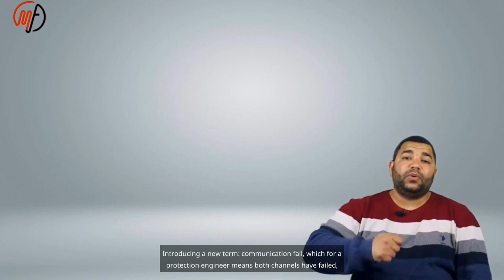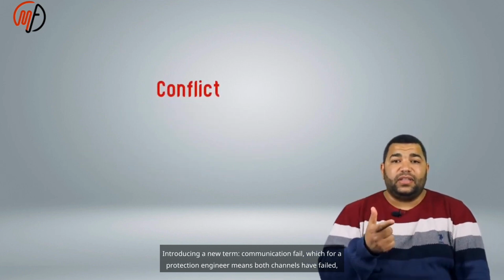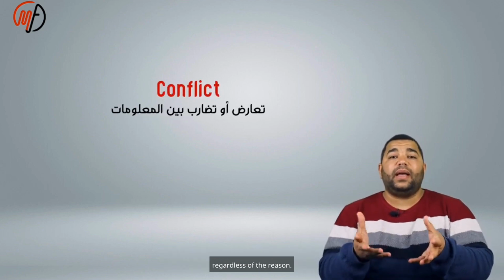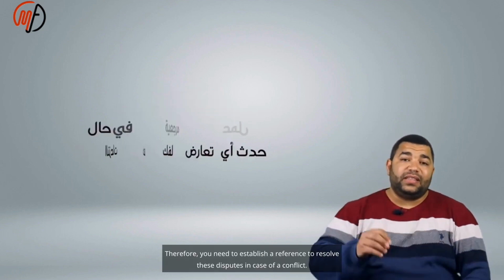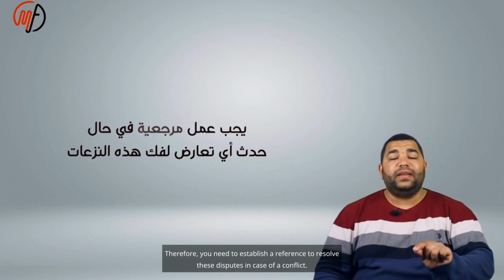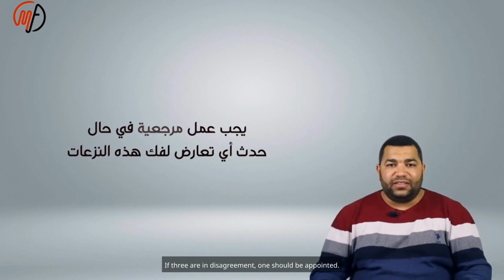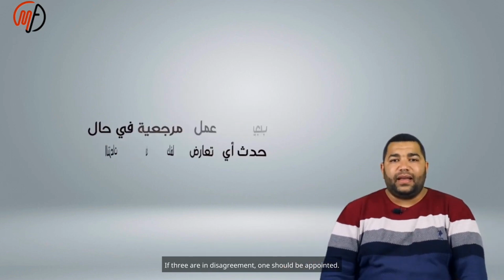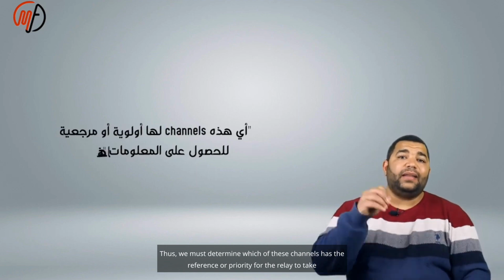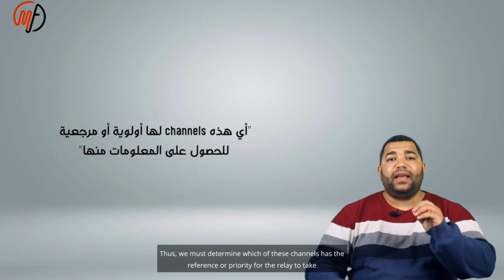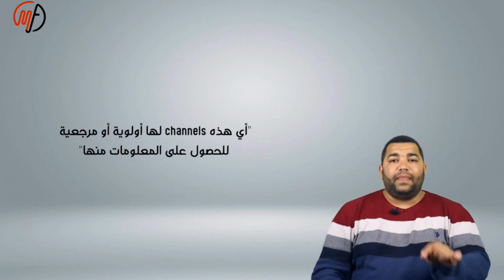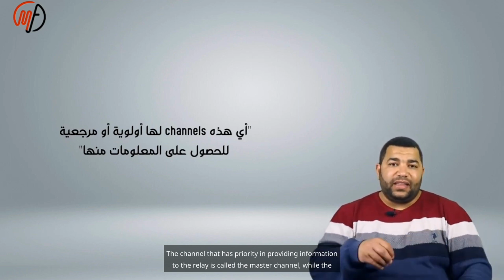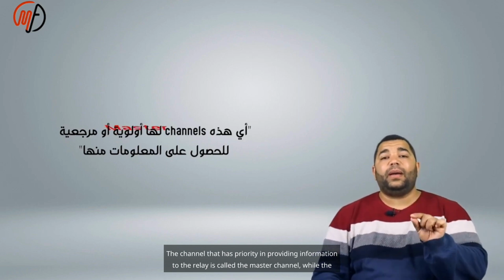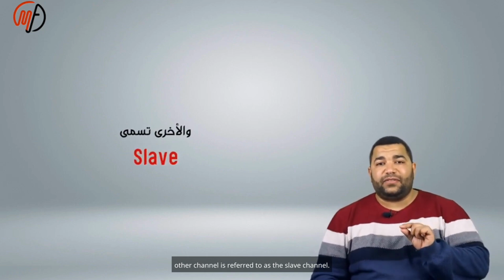Introducing a new term, communication fail, which for a protection engineer means both channels have failed, regardless of the reason. Therefore, you need to establish a reference to resolve these disputes in case of a conflict. If they are in disagreement, one should be appointed. Thus, we must determine which of these channels has the reference or priority for the relay to take information from. The channel that has priority in providing information to the relay is called the master channel, while the other channel is referred to as the slave channel.